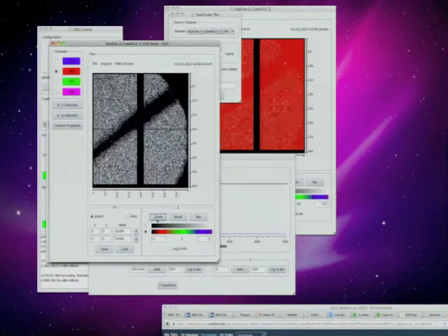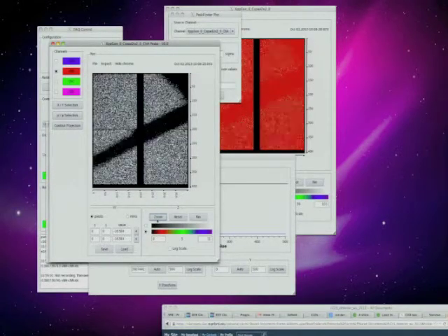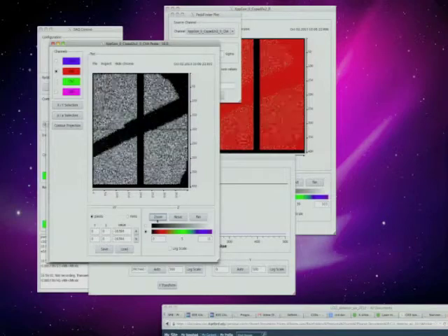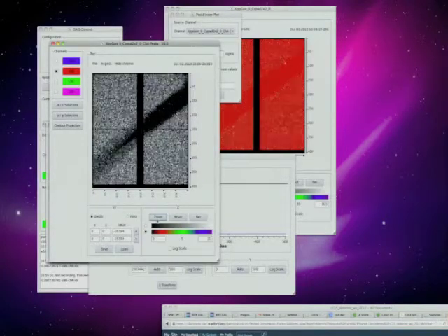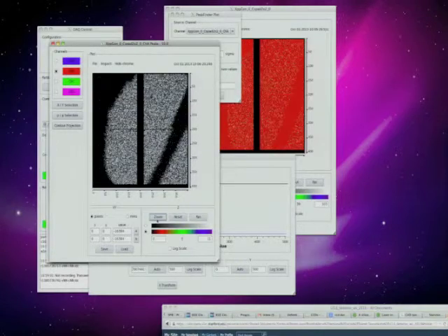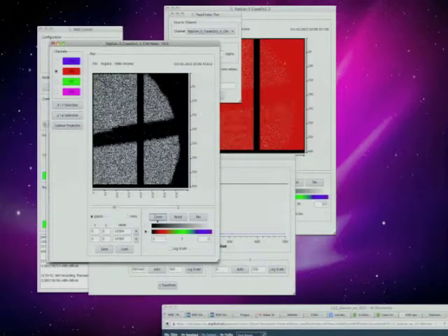So now when we turn this, you can see it turns. So, I mean, it's live, it's real time. And you see the advantage of having basically a video speed X-ray imager. Because when you're moving your stages or whatever, you get immediate feedback of what you're doing.